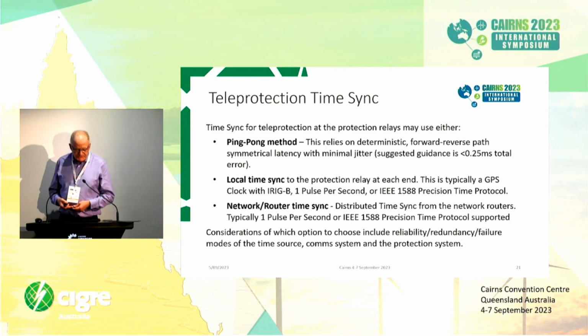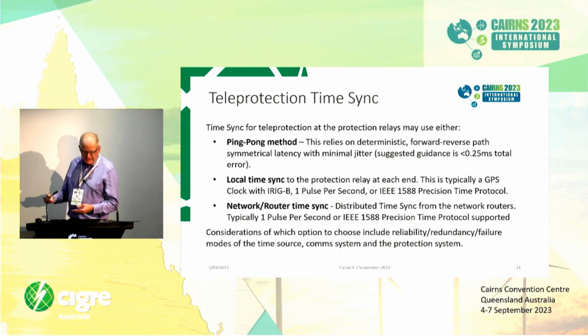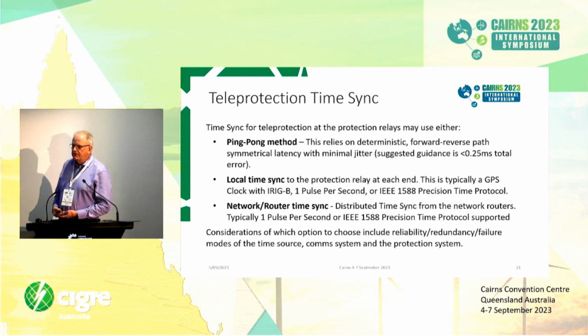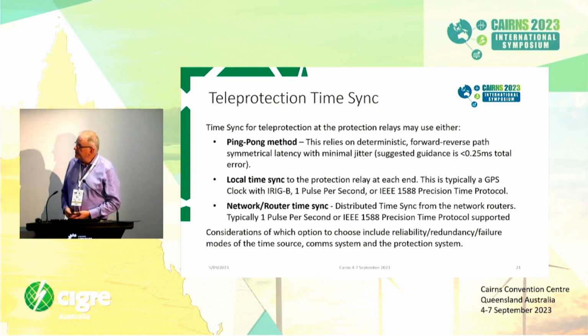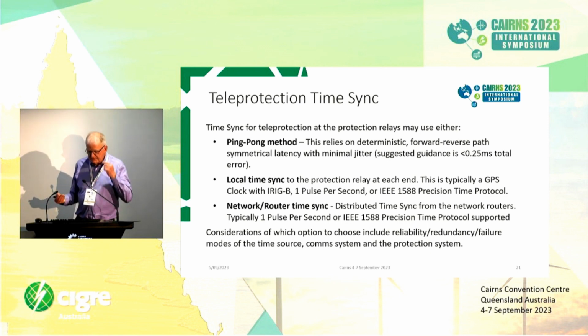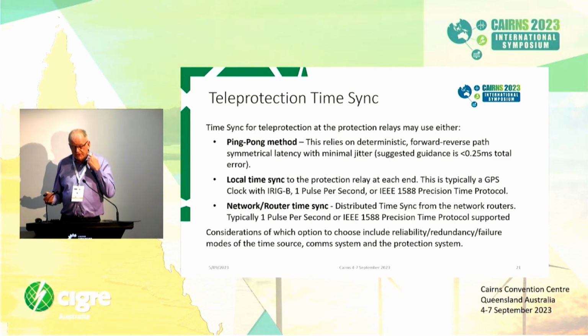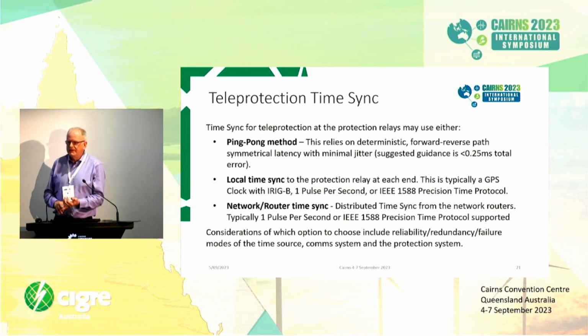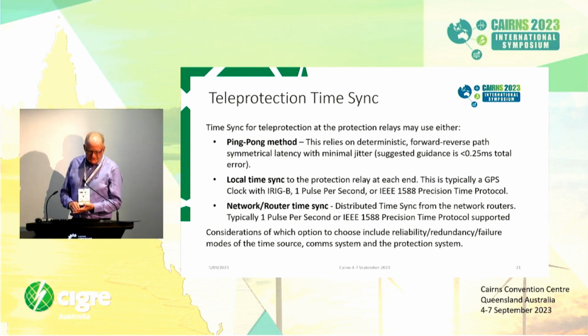We can also use local time sync to the protection relays at each end. Typically this could be via GPS through a clock at the substation using a 1 pulse per second input on the relay, or it could be using precision time protocol as well. Or alternatively, you could use some sort of distributed time sync from the communications network itself using SyncE or some other means across the network. Considerations of which options to choose include the reliability, redundancy and failure modes of the time synchronisation system, the communication system and the protection system. But typically I'd say that if a protection relay offers a local time sync method, you should probably use that over and above using the ping pong method.